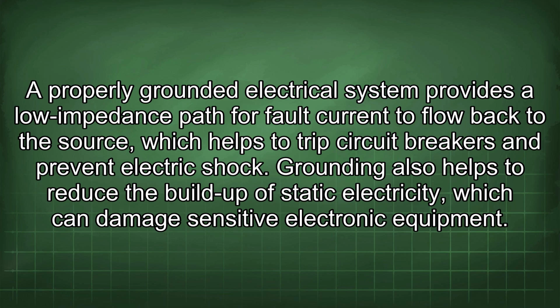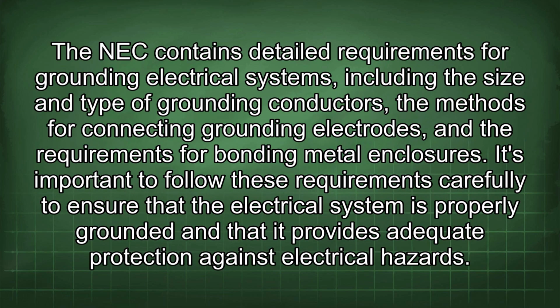Grounding also helps to reduce the buildup of static electricity, which can damage sensitive electronic equipment. The NEC contains detailed requirements for grounding electrical systems, including the size and type of grounding conductors, the methods for connecting grounding electrodes, and the requirements for bonding metal enclosures. It's important to follow these requirements carefully to ensure that the electrical system is properly grounded and that it provides adequate protection against electrical hazards.